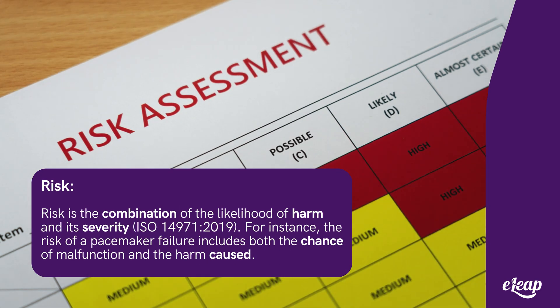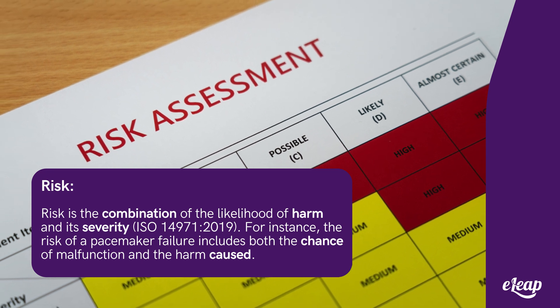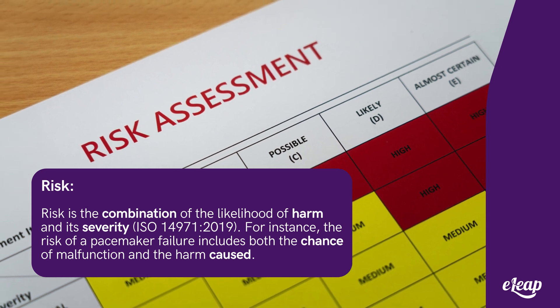Risk is the combination of the probability of occurrence of harm and the severity of that harm (ISO 14971:2019, clause 3.19). For example, the risk of a pacemaker malfunction combines the likelihood of failure and the severity of the impact, which could range from minor inconvenience to serious injury or death.